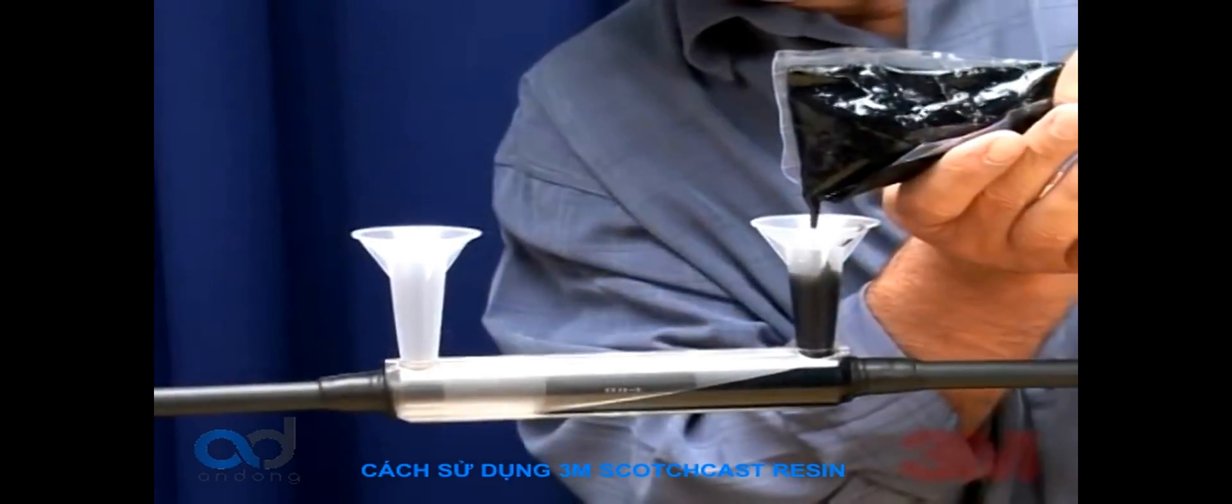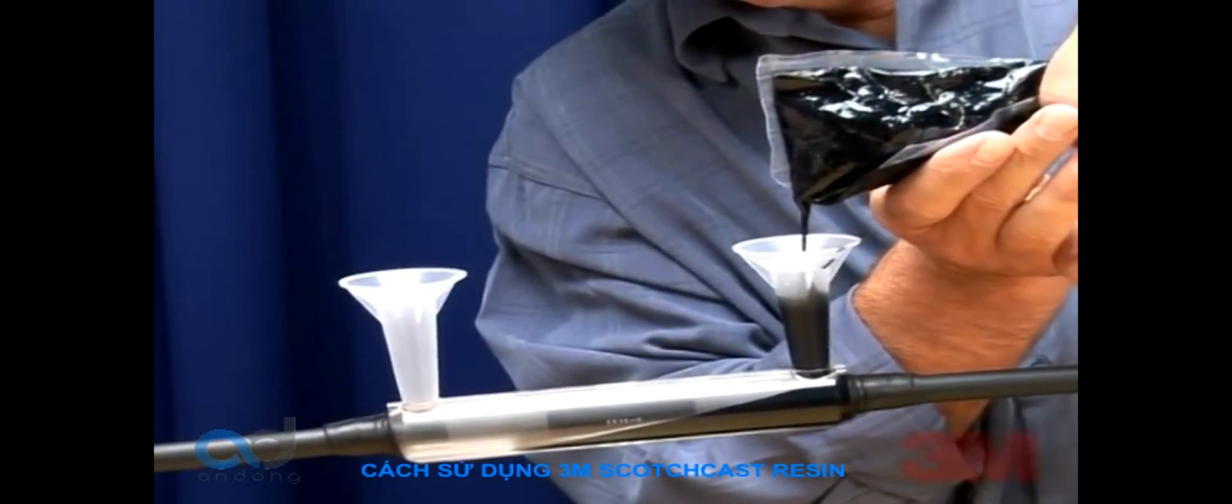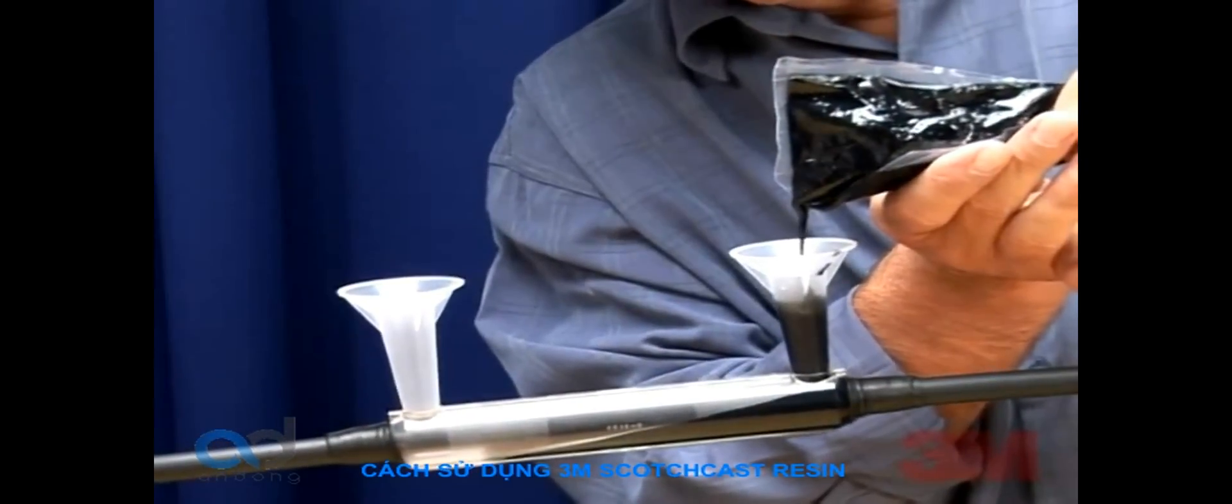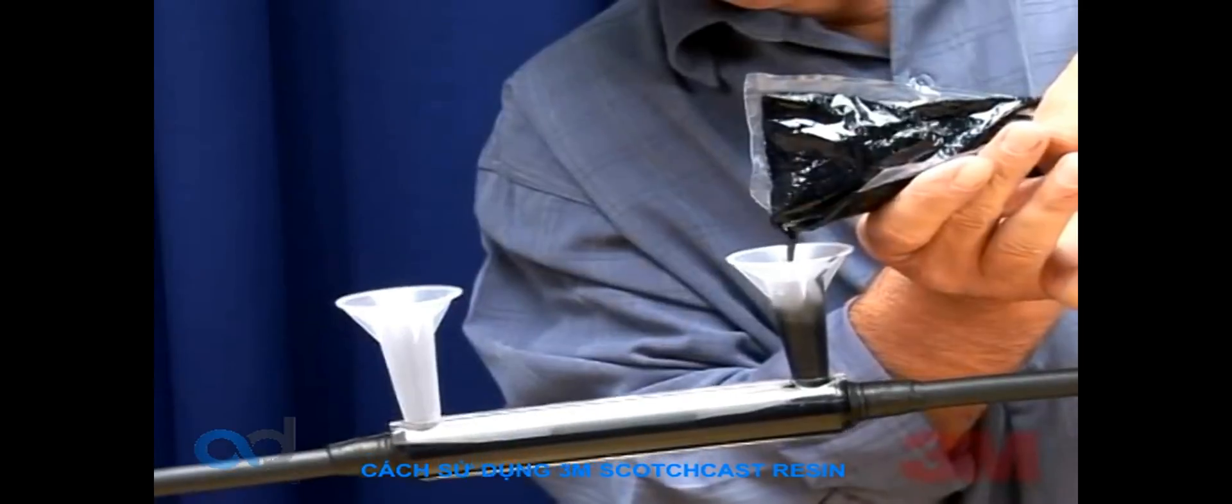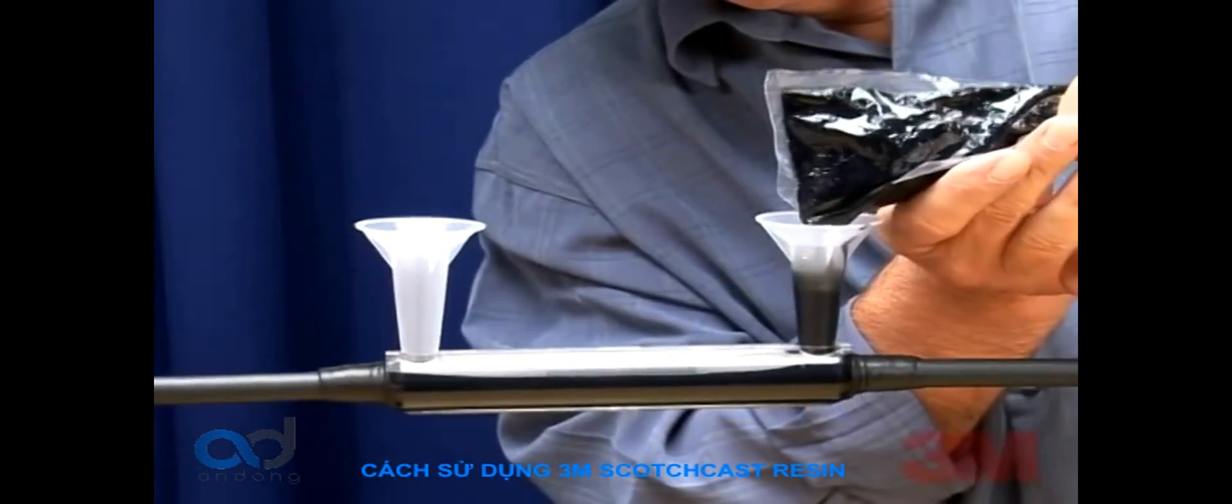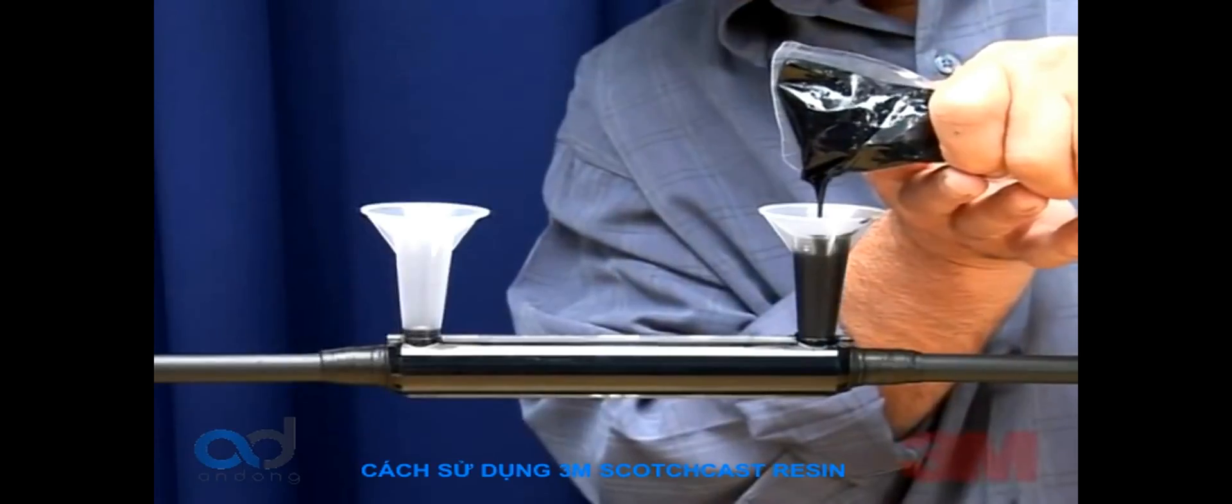When the resin has solidified and cooled, the splice may be put into service. A helpful hint: tilt the splice slightly and pour resin in the downhill side spout if area permits. This will push the resin to the raised end spout pushing excess air from the splice.